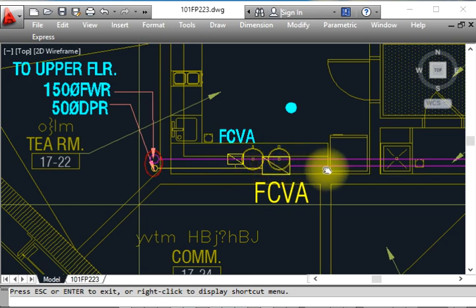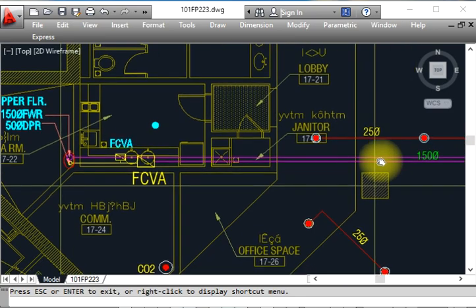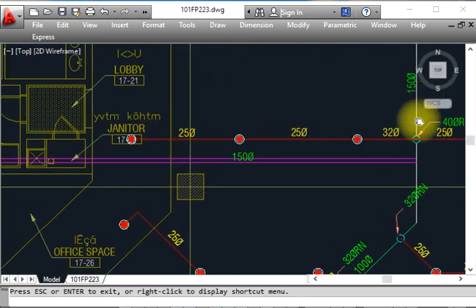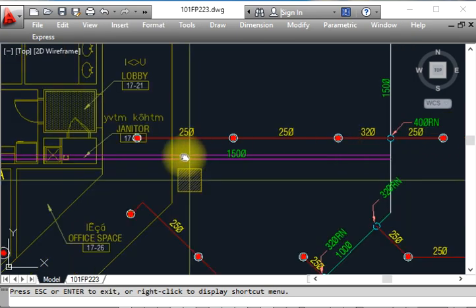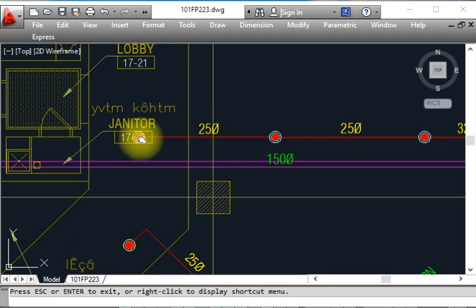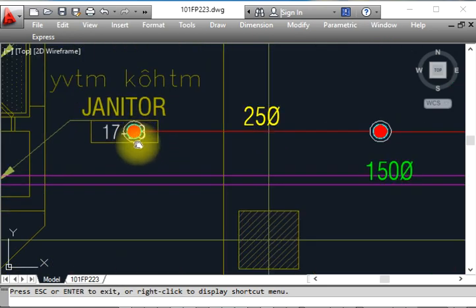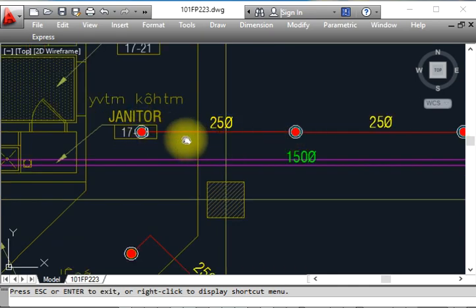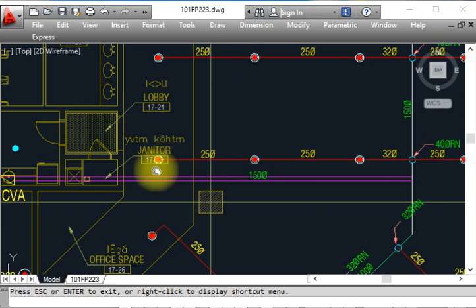This pipe is going here and this small pipe is coming for all areas. This is the main pipe — 150mm diameter going to the air here with two main pipes. We start distribution for firefighting water from here. These are pendant type sprinklers. The dimension here to here should be 3 meters, and here to here should be 4 meters. We distribute the pipeline 3 by 4 because per NFPA 13 one sprinkler should cover 12.3 square meters.